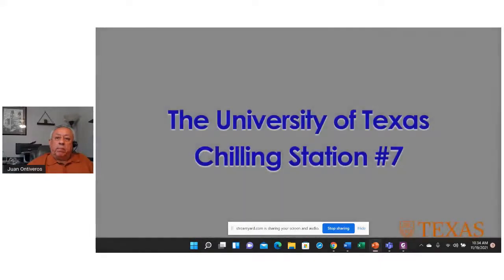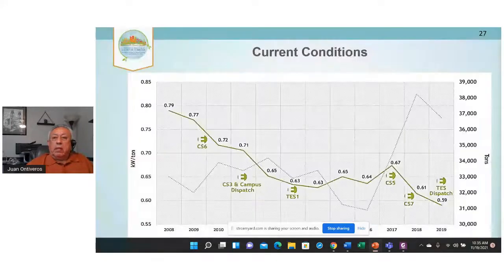One of the big advantages we had with this plant is that we could build the exact cooling tower that we wanted. So we decided to build the plant with a 5-degree approach. So it's a much bigger tower. And in actuality, we've been able to run most of the year with a 2-degree approach. That really has helped us make this plant really, really efficient.